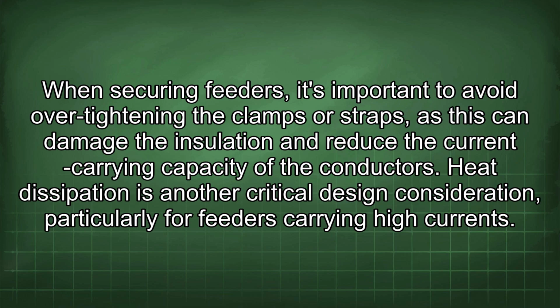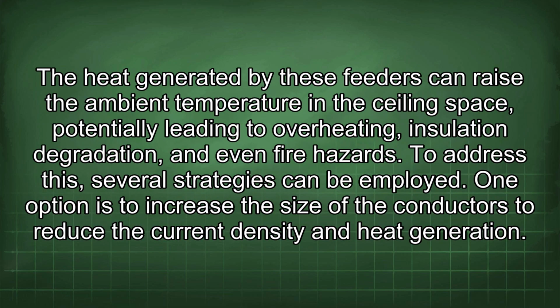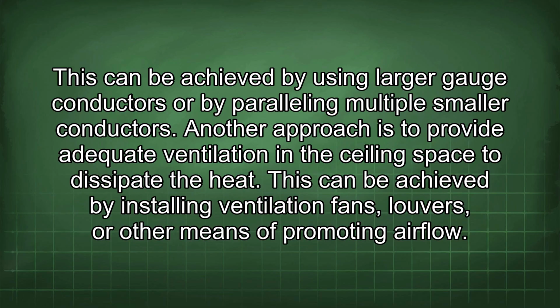Heat dissipation is another critical design consideration, particularly for feeders carrying high currents. The heat generated by these feeders can raise the ambient temperature in the ceiling space, potentially leading to overheating, insulation degradation, and even fire hazards. To address this, several strategies can be employed. One option is to increase the size of the conductors to reduce the current density and heat generation. This can be achieved by using larger gauge conductors or by paralleling multiple smaller conductors.